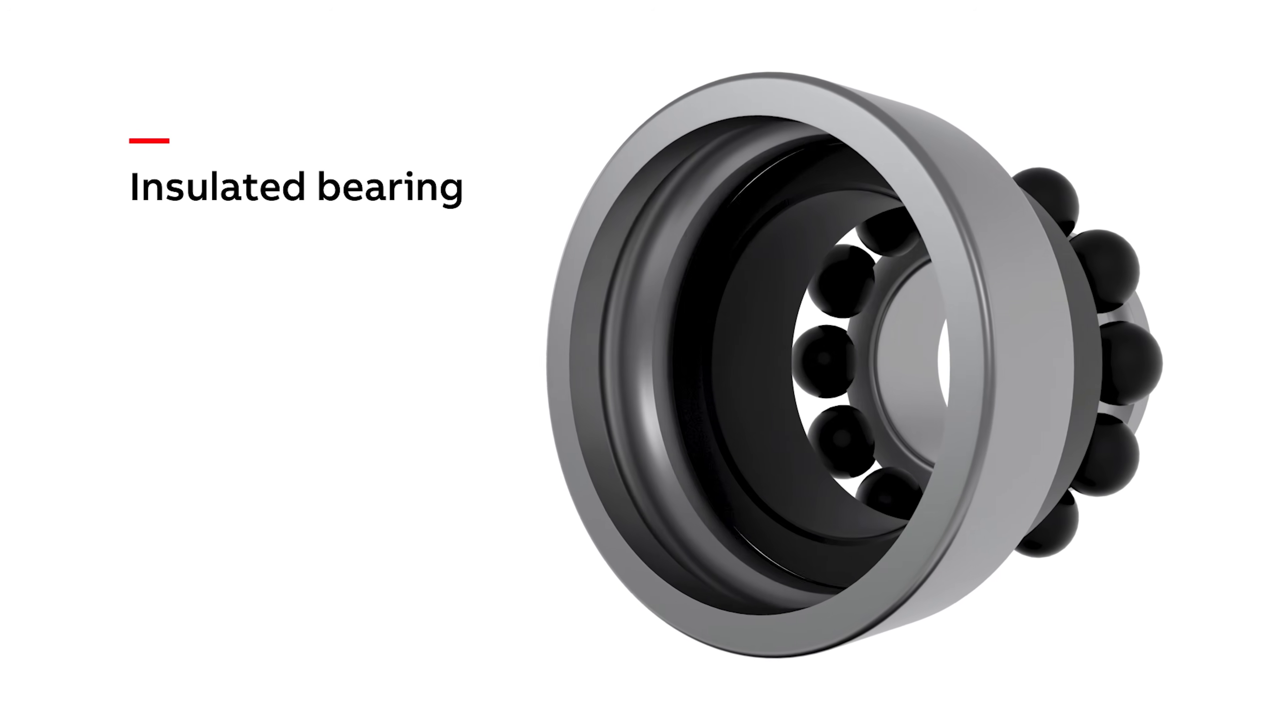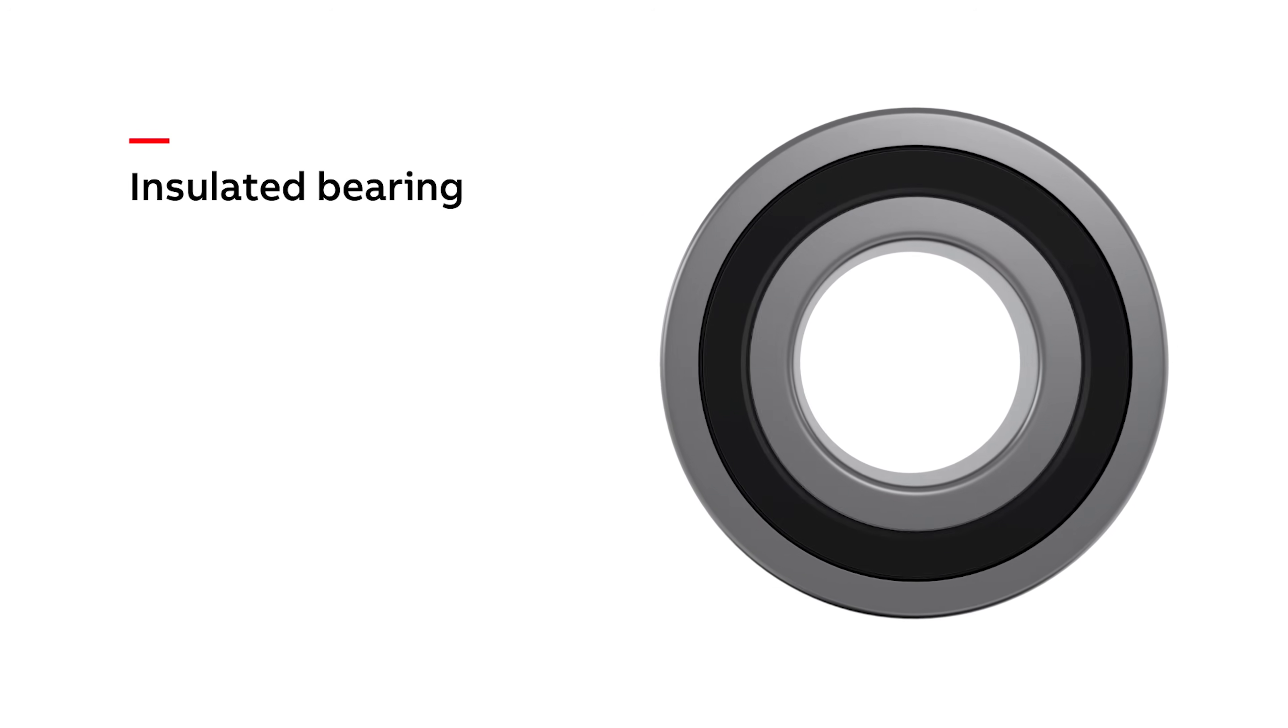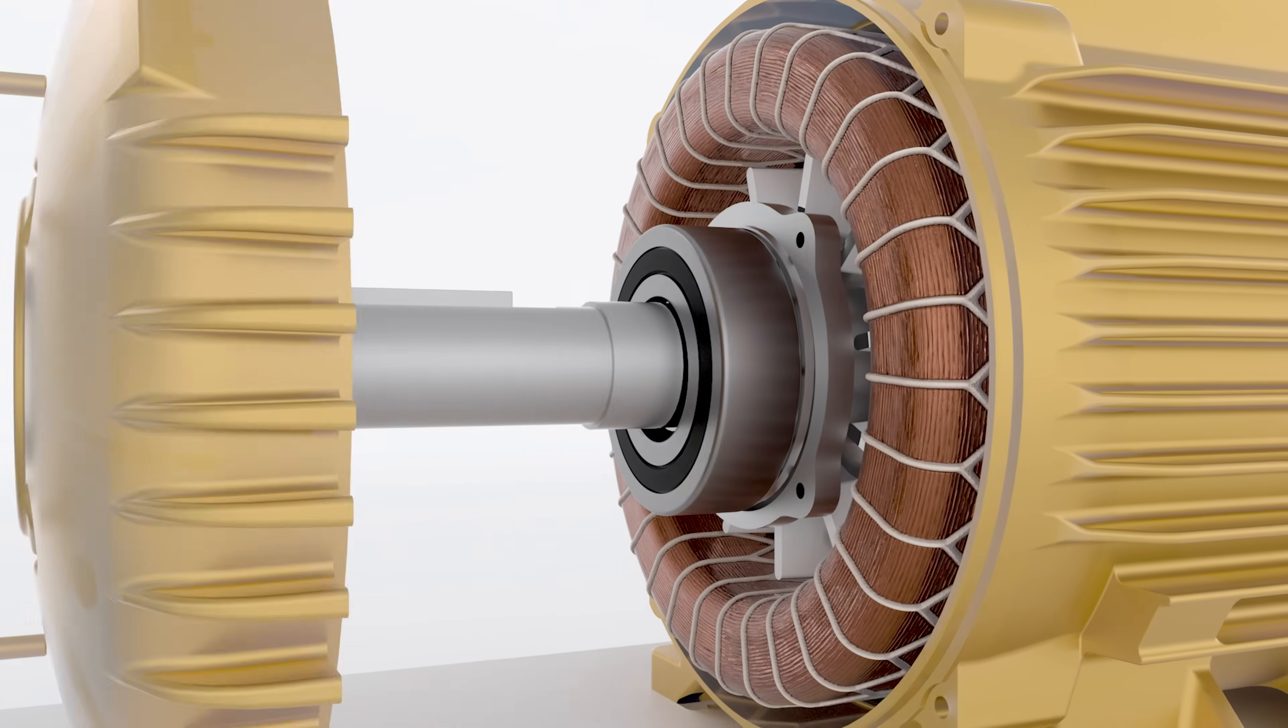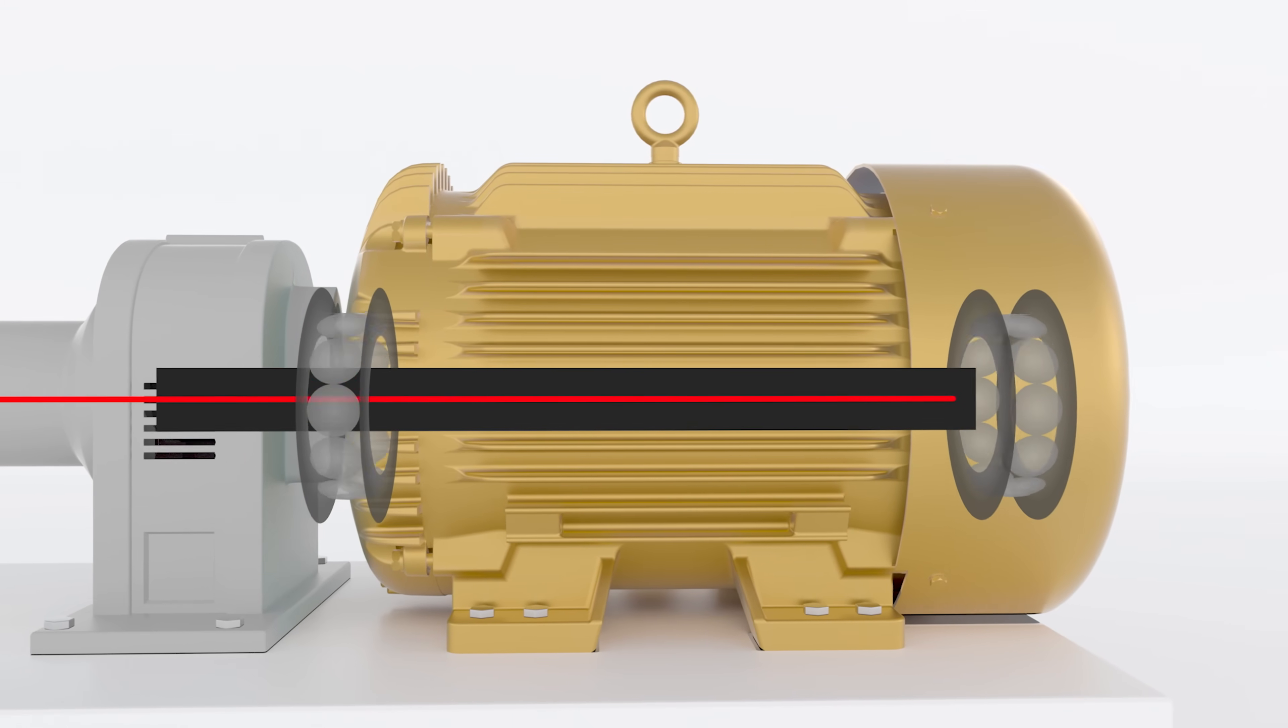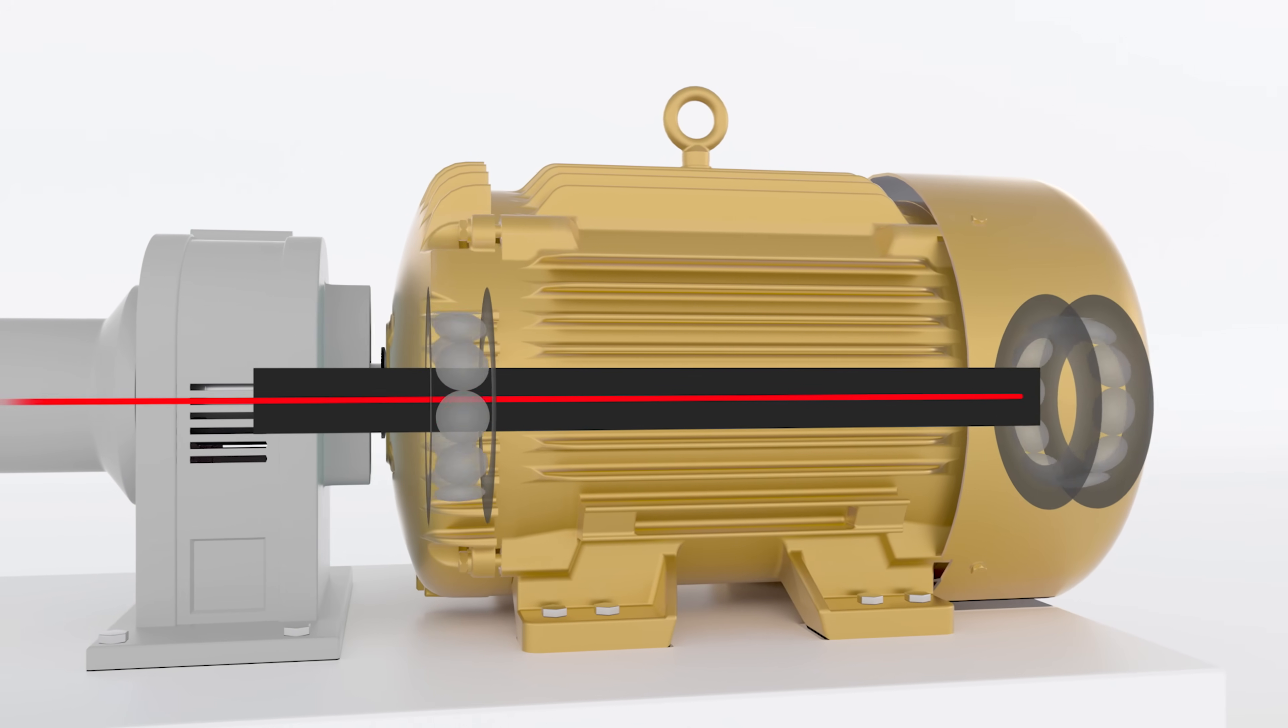Bearings made from an insulated, non-conducting material, such as ceramic, are another solution to eliminate the discharge of current through the bearings. Non-conductive ceramic materials prevent shaft currents from flowing through the bearings and damaging the motor. Since no electrical current flows through the motor bearings, there is no chance of current-induced wear.